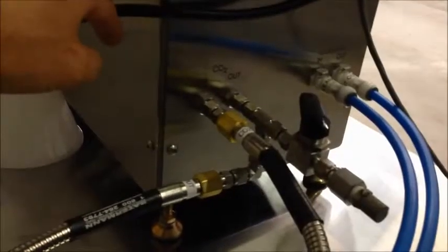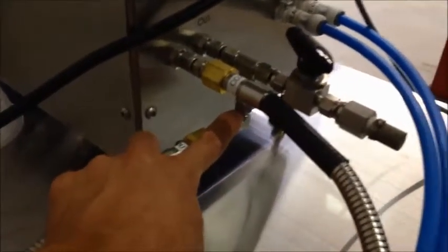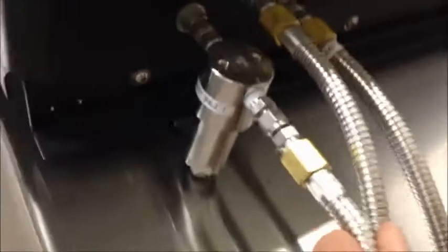Your braided hoses, they should be labeled, but if they're not, pump outlet should go to CO2 inlet right here. Pump inlet right here should go to CO2 outlet. This one down here, right here. Ensure that the coalescing filter is orientated the right way. Flow is going to be coming this way. There should be flow marks somewhere. There they are down here. So there's a flow mark right here showing which way the flow is. It's going to be going into the pump.